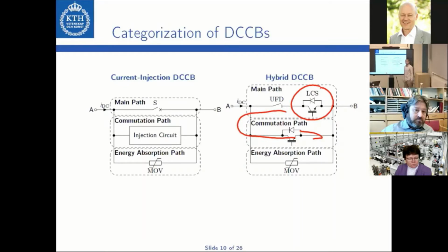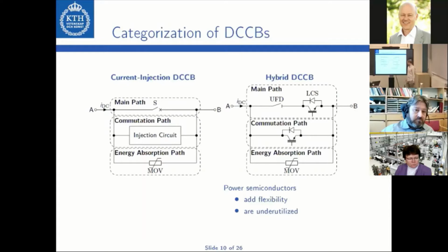The semiconductors in the commutation path then turn off to interrupt the current flow. Both concepts use a metal oxide varistor in the energy absorption path, which is quite typical, as I mentioned before. The thing about the hybrid DCCB is that the power semiconductors add a considerable advantage, which is flexibility, since they can be switched easily. And the thing is, though, that these power semiconductors are underutilized in this application.